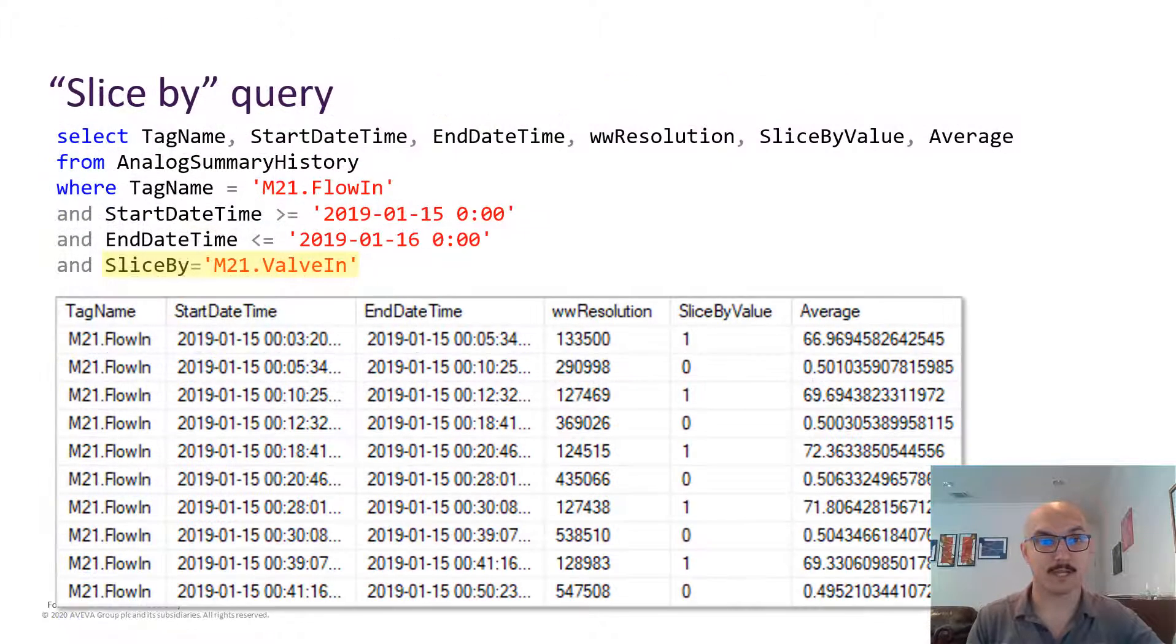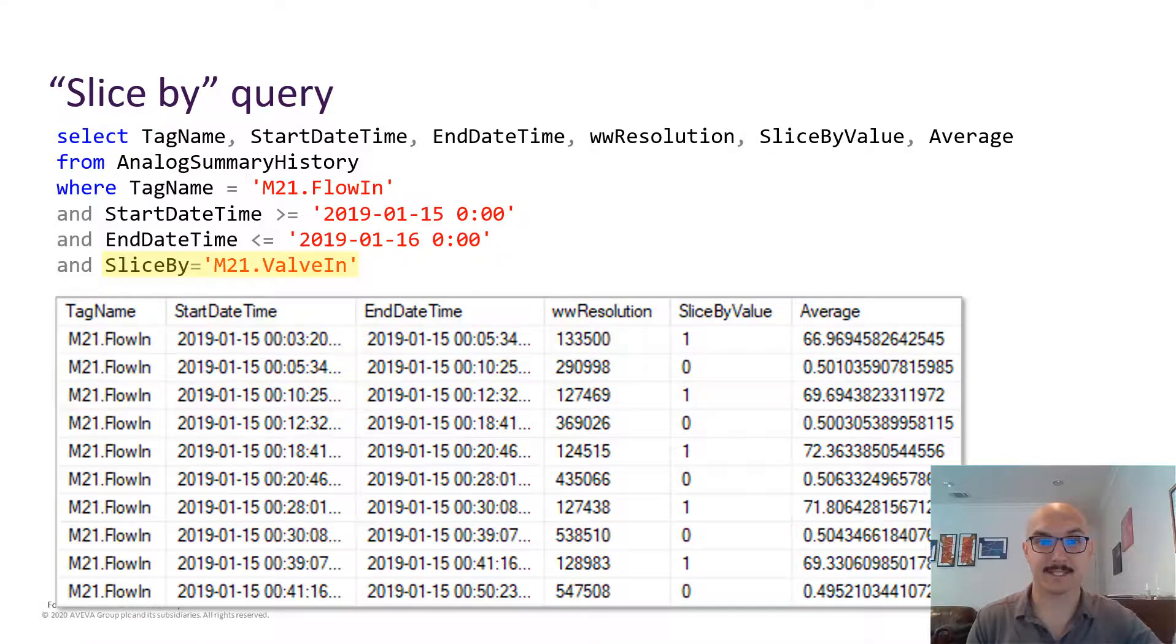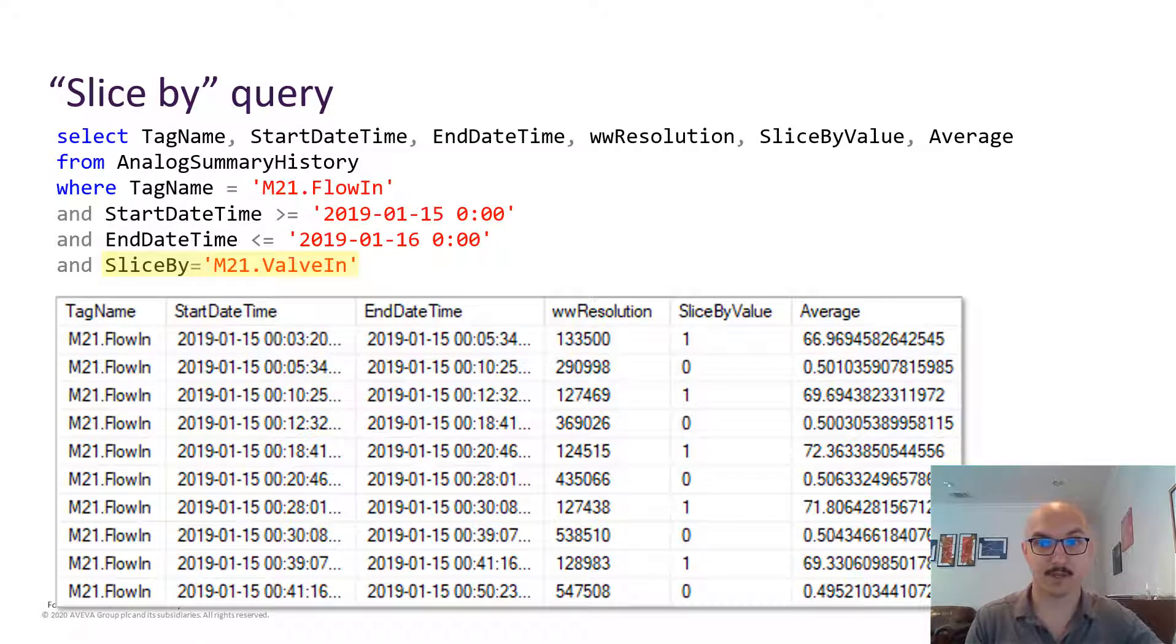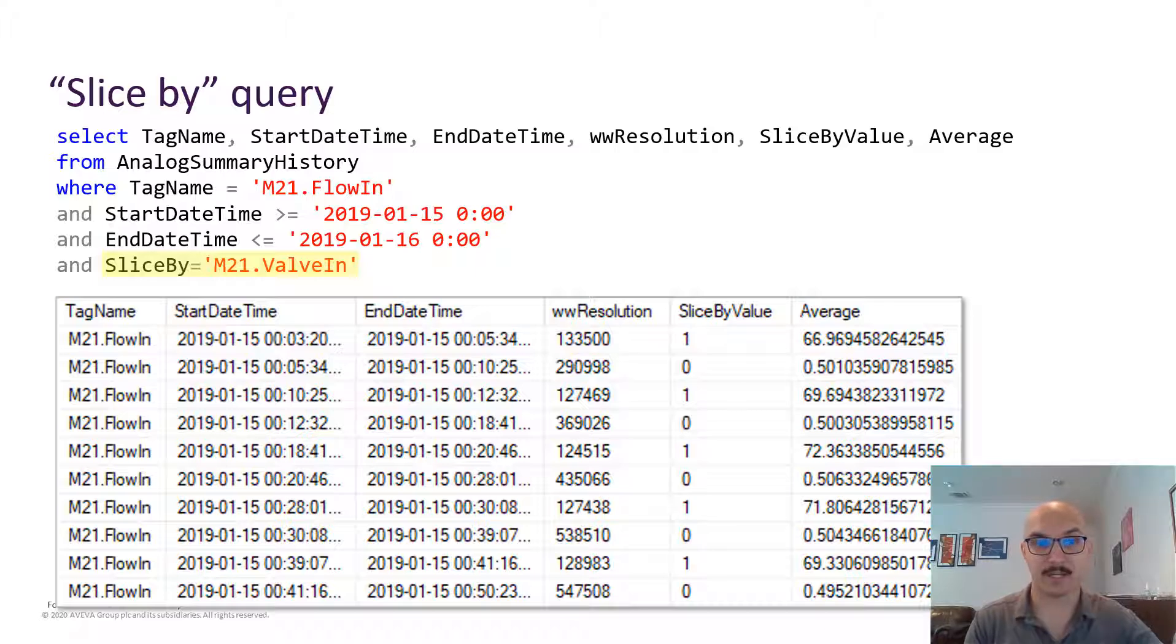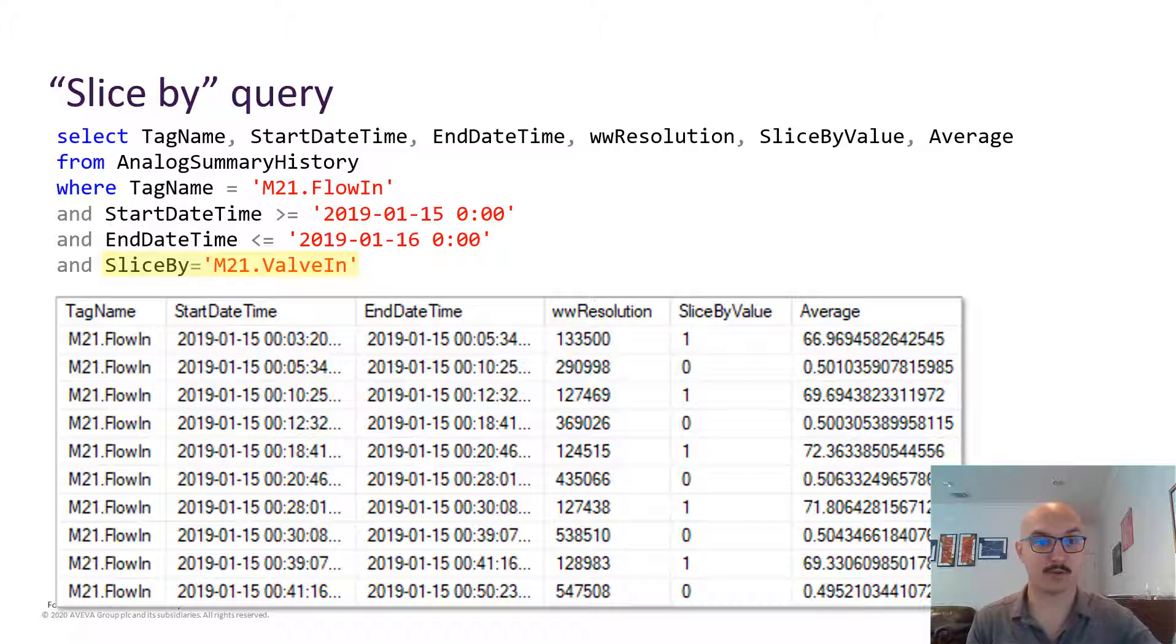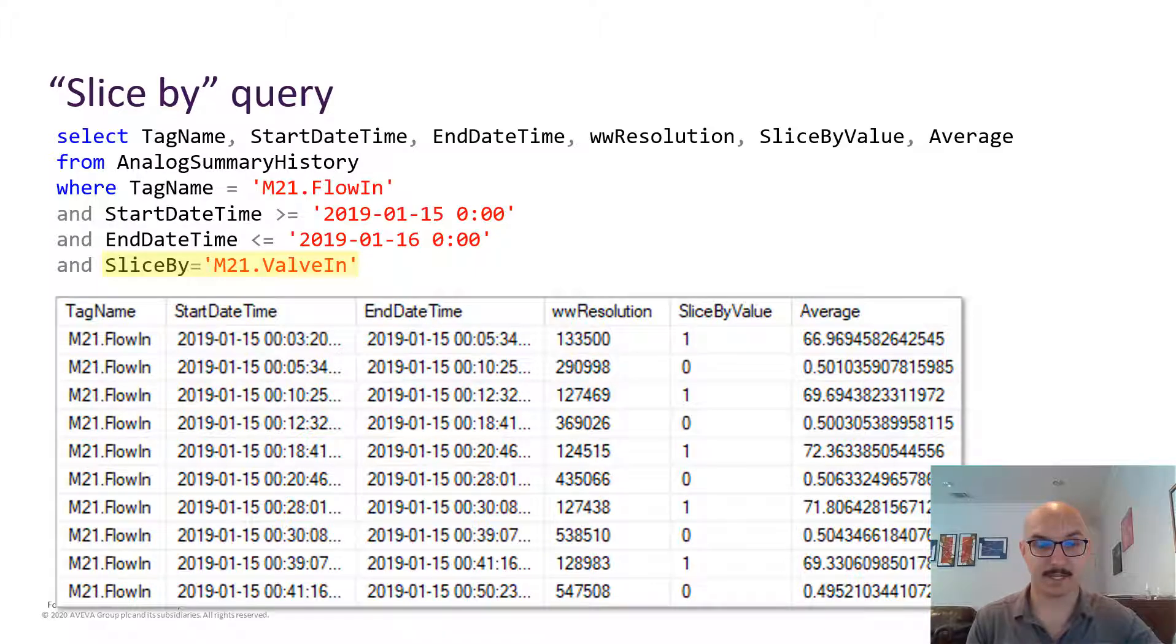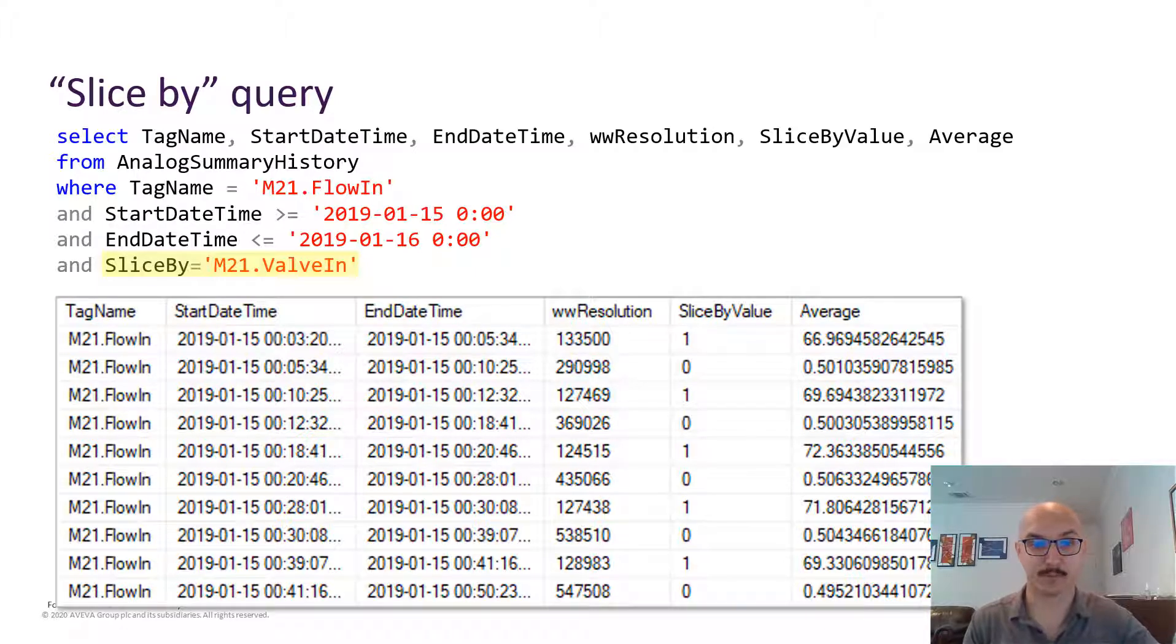Now in the historian there's a slice by function available where you can add this to your SQL statement and add a where condition that includes a slice by variable. This variable can be a discrete, it can be an integer, or a string variable.